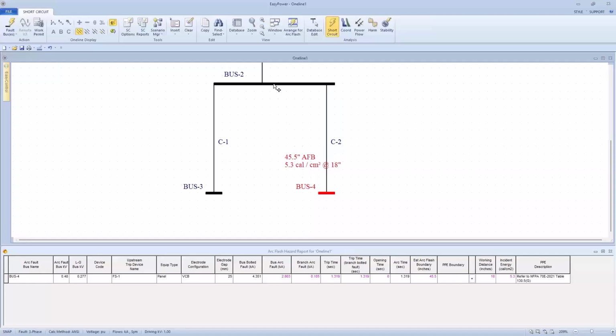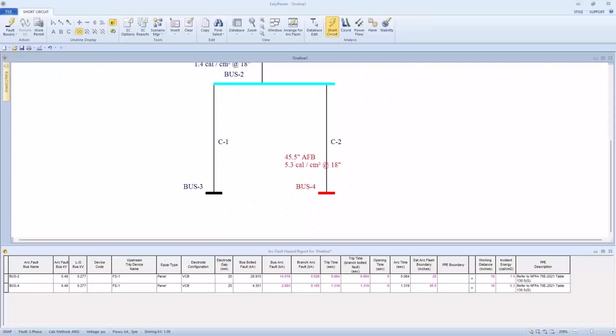In fact, if I select this bus, hold down Control and select this bus, and then fault both buses, I'll see that my trip time on bus 4 is over 20 times longer than it would have been on the secondary of the transformer. And so during that time, my 4-calorie PPE would not have been enough to protect me from that arcing energy. Well, I call this the arc flash paradox.